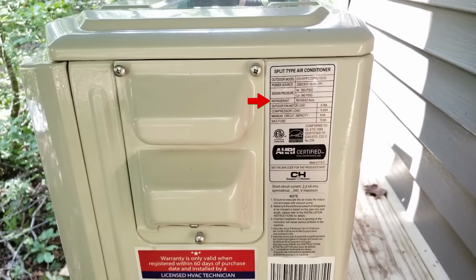Absolutely. Yeah, that's the thing, because when you recover the refrigerant charge out of the system, you turn the system off and you recover all the refrigerant. You're going to see if the system is low compared to the factory charge that's listed on the outdoor unit rating plate. And then you also have to, in some cases, guesstimate the line set length and the path, because a lot of times you can't see it, it's in the walls. So you see where the indoor unit is, and you're measuring the floor length and then the heights. And when there's multi-zones, you're adding it all together to come up with a cumulative line set length.